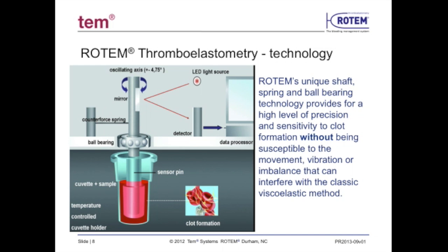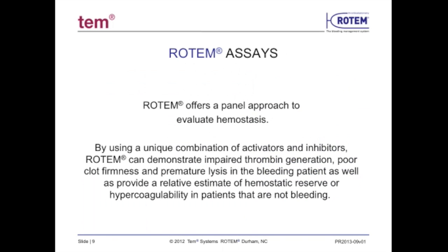It is called rotational thromboelastometry because the pin rotates within a fixed cup. This unique system is precise and sensitive to clot formation without being sensitive to vibration, imbalance, and movement that can disrupt the classic TEG method.